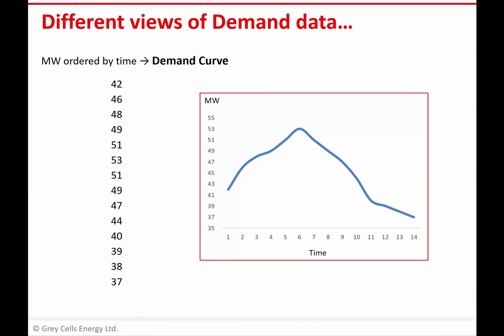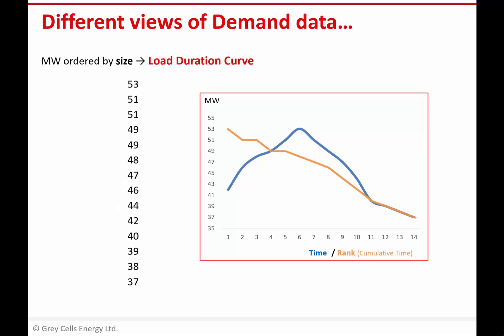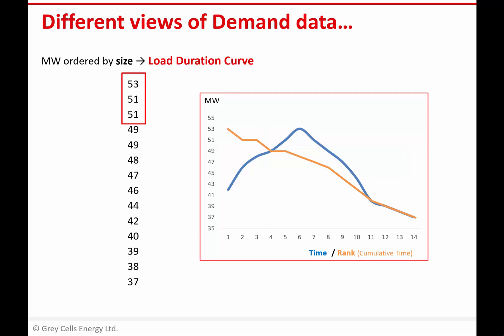There is another way of analysing that exact same data, however, which makes the task of seeing how often power is above a certain level much more straightforward. If I go back to my simple data set, another way I can plot that exact same data is to order it not by time but by size. So I've basically sorted that list so all the larger numbers are at the top and the smaller ones at the bottom, and then I'm plotting that data to produce the yellow line here. That yellow line is what we call a load duration curve. In this simple example, if I want to know how many time periods the demand was above 50 megawatts, I can read that off the chart or simply count off the number of occurrences above 50 megawatts.